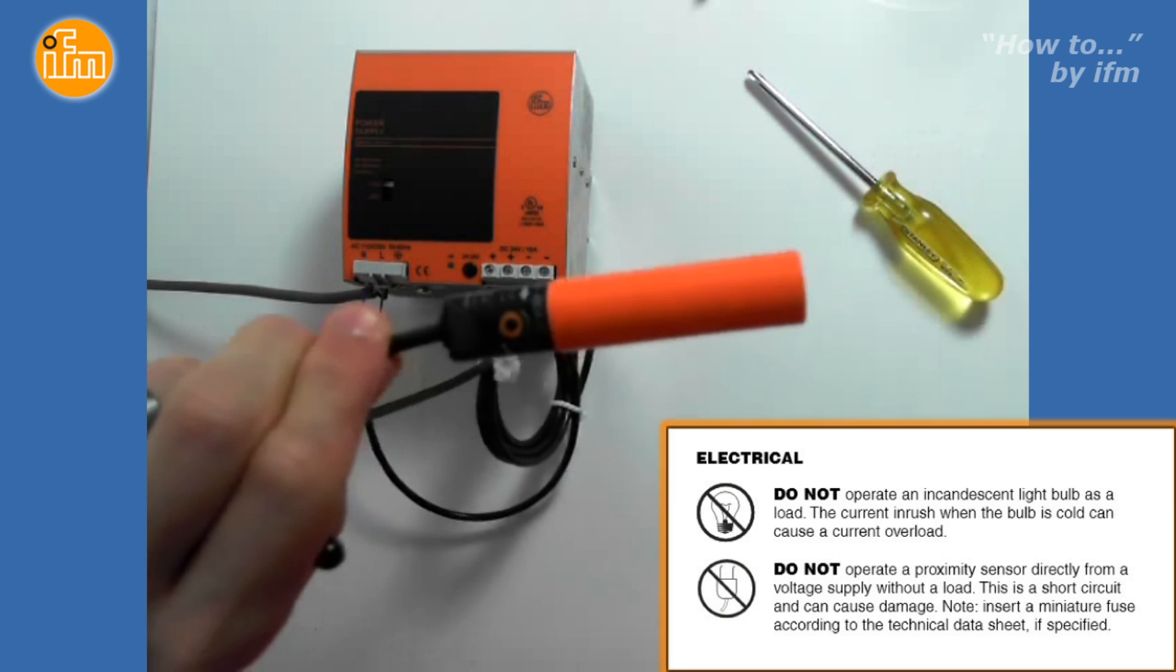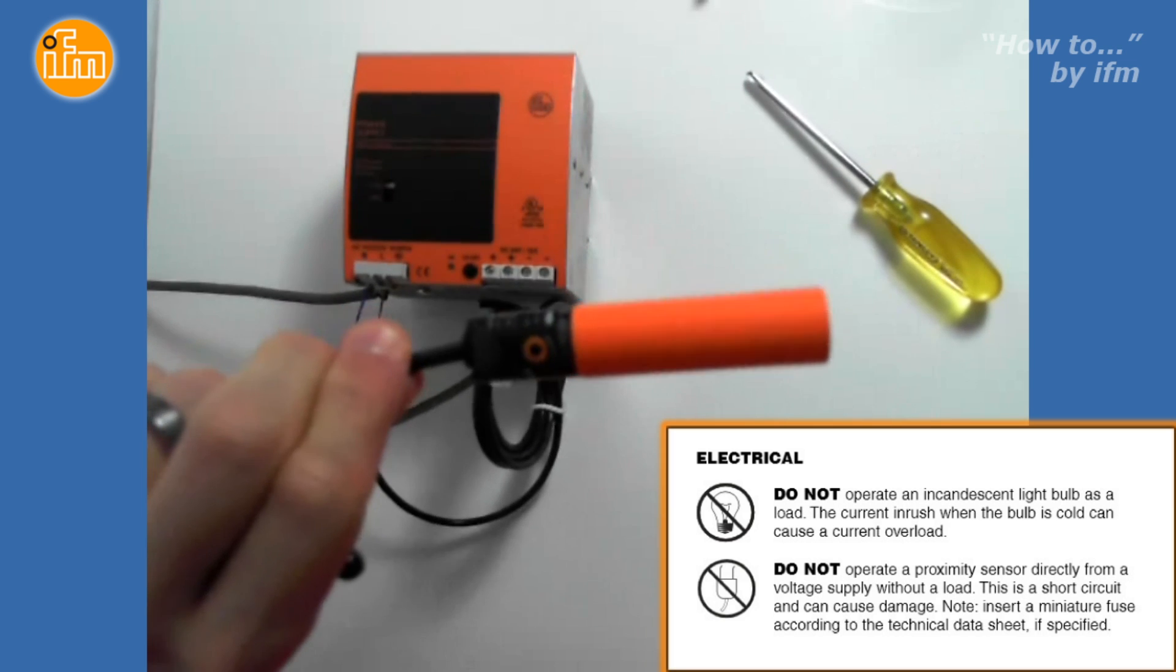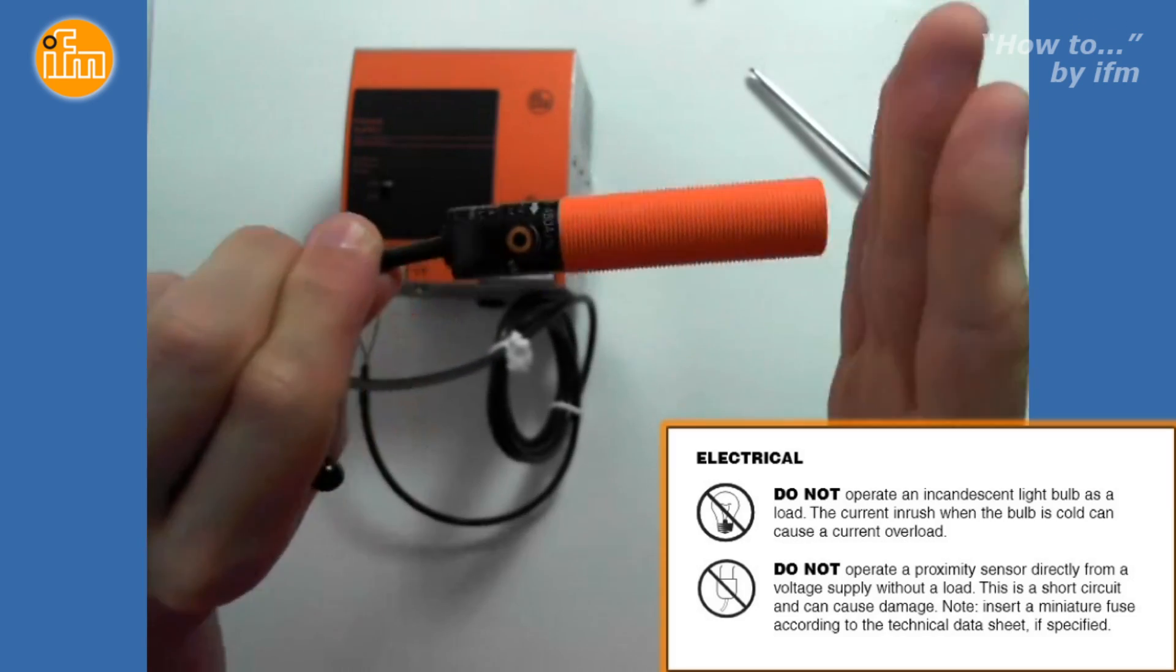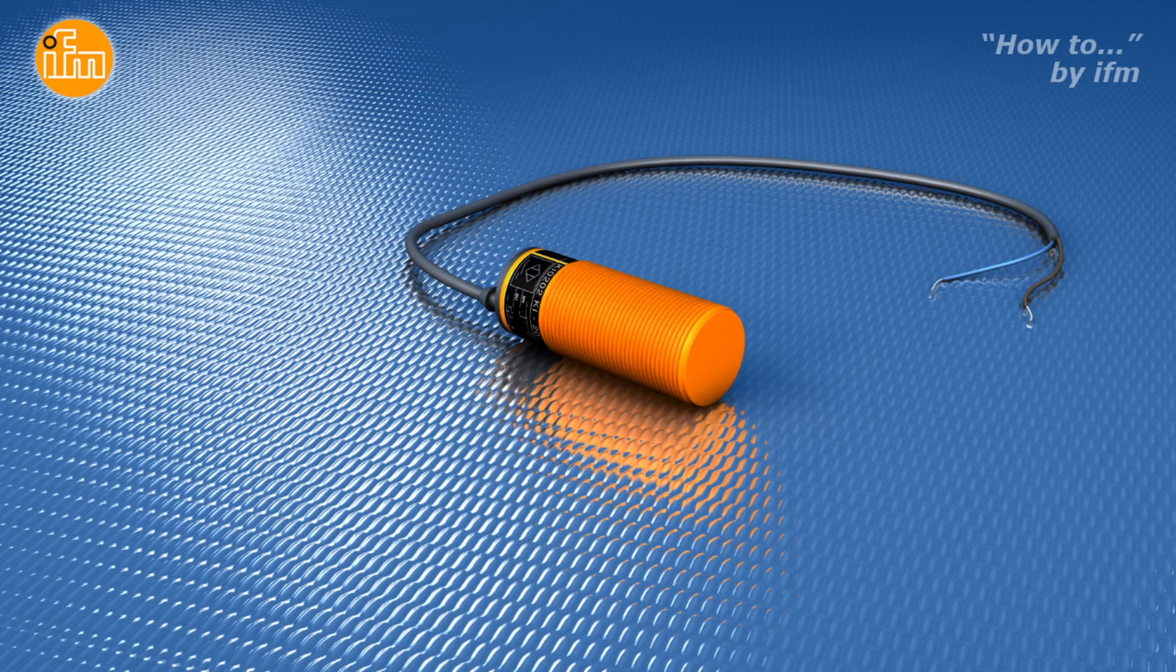A load must be used for proper function of the sensor. It is important to note that an incandescent light bulb should not be used as a load because the current inrush from a cold bulb can cause an overload condition.